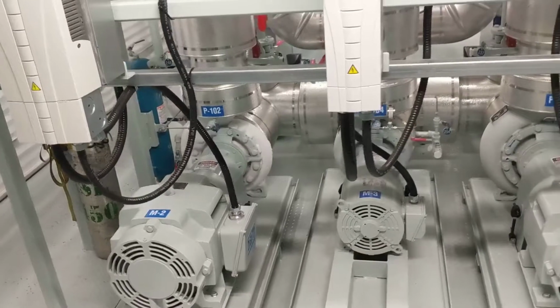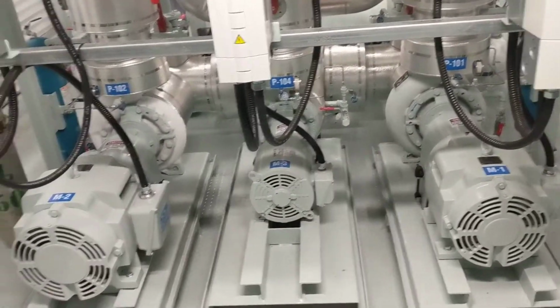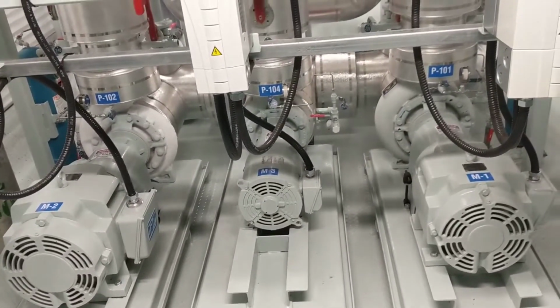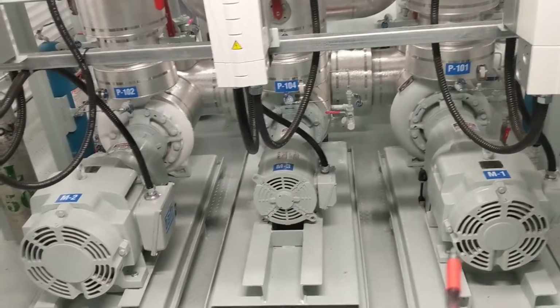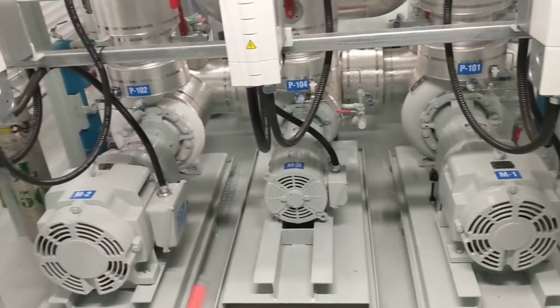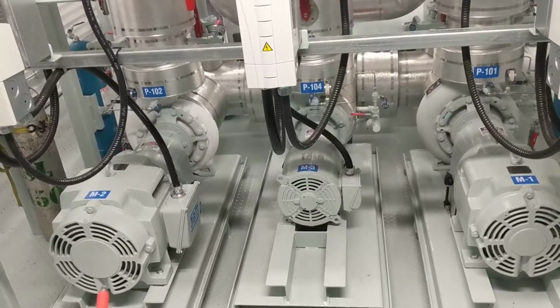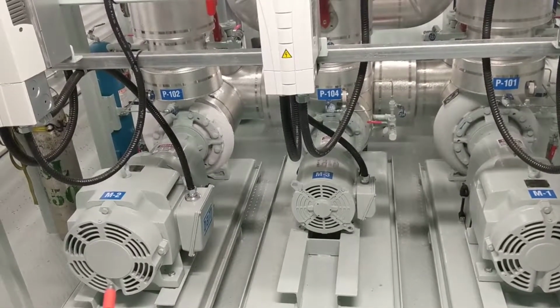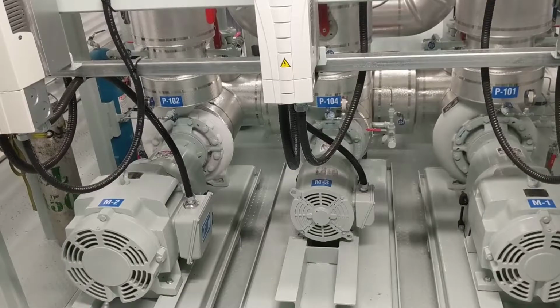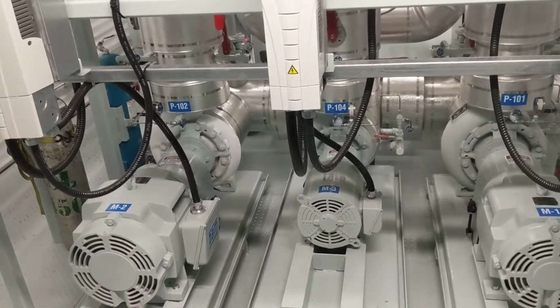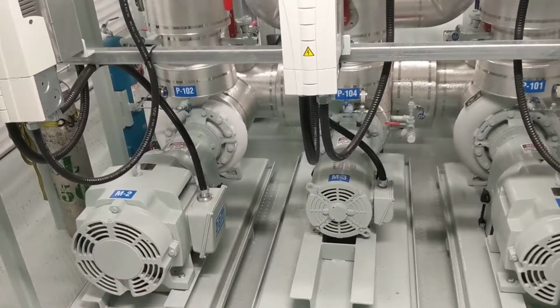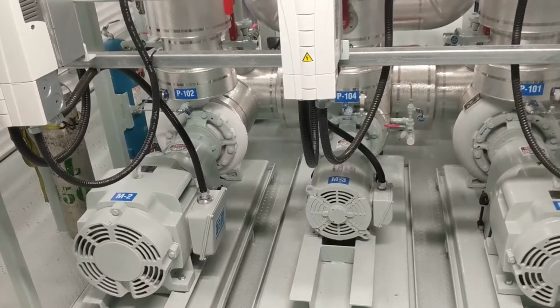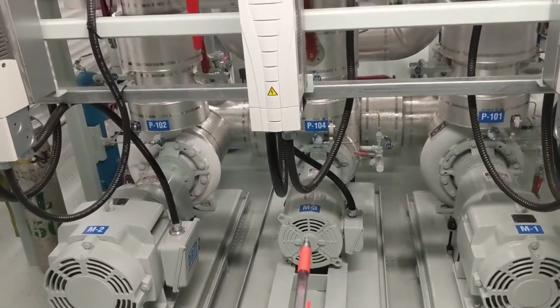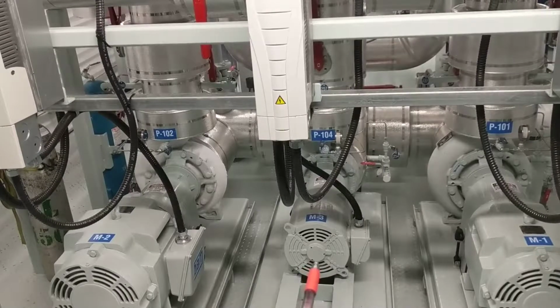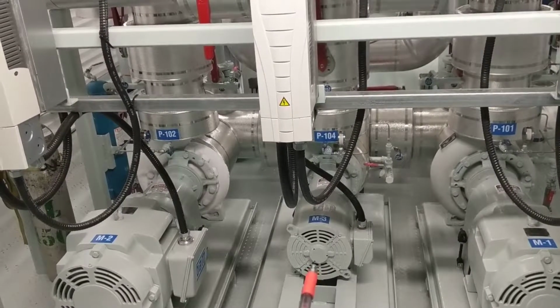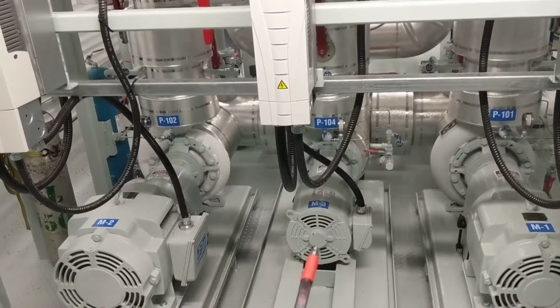When you're looking at the brine pumps, you should easily be able to tell which one is for which arena. So if you look at them, you can see there's a difference in size. This biggest one here is for the AK arena because it is the furthest away in terms of the amount of GPM that are flowing. So the curling rink is fairly far, but it has a lot less brine lines in it, and it has a lot less brine flowing through it. So therefore it's a much smaller motor.